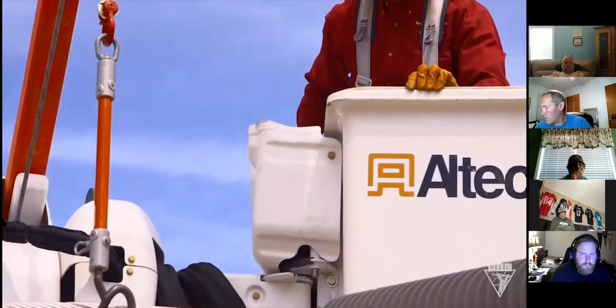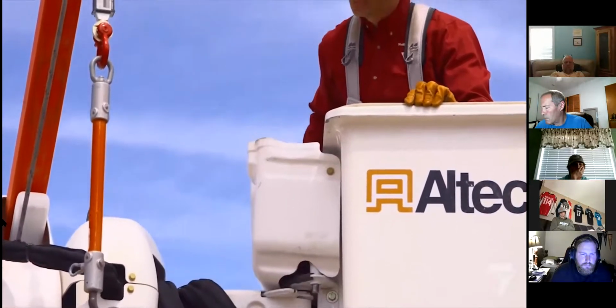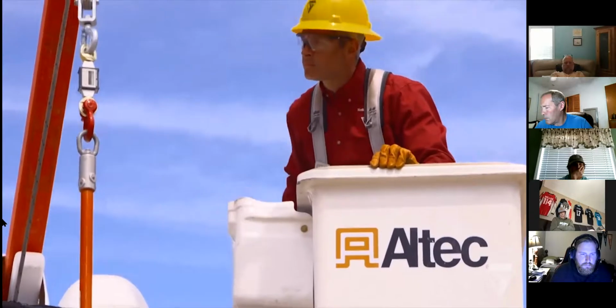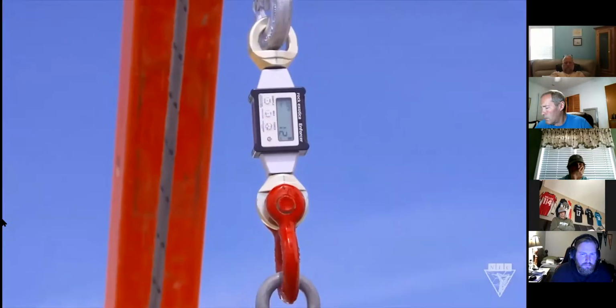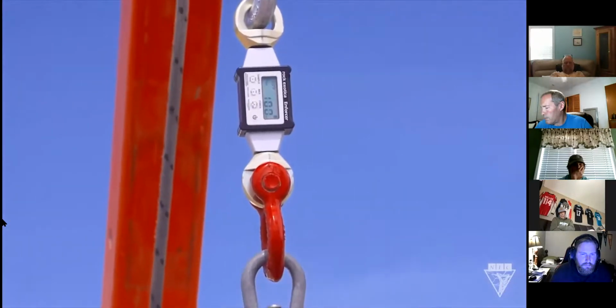But let's say I need to use a jib to lift up a wire. It gets a little more tricky because obviously conductors don't have nameplates with the weight written on them. But there's a couple things you can do to figure it out. If you're using a link stick, NLC recommends having a small dynamometer in each truck. This is the best way to monitor the weight you're lifting and make sure you never cross your limits. If you don't have access to a dynamometer, or if you're using a wire holder, you can contact the engineering department to get the weight or do some simple calculations.